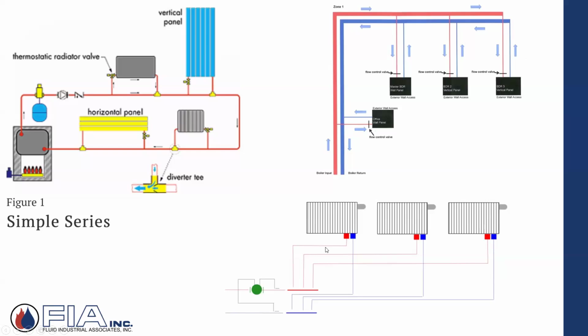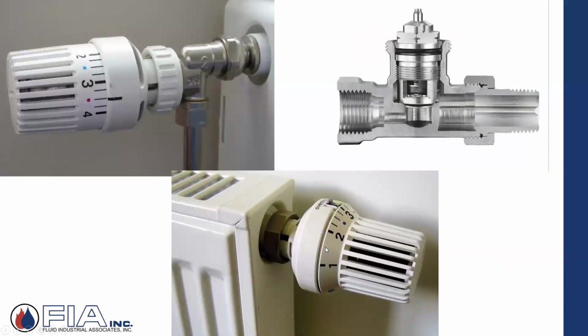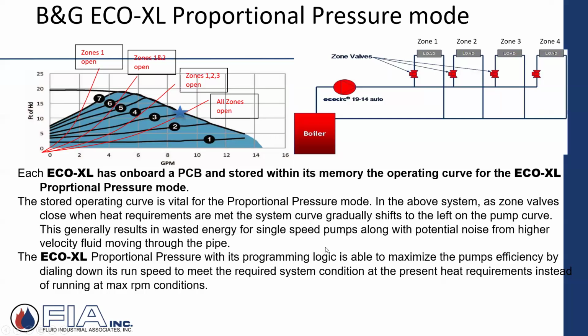These just happen to be non-electric valves as opposed to electric, but they could be electric. It doesn't matter. But it's a two-pipe system feeding terminal units. And those terminal units have a valve that closes so that they don't overheat the space. Pretty simple, pretty straightforward. This would be an exploded view of a non-electric valve where there's no wires. It's just sensing. This is popular in dormitories, maybe apartment buildings where they don't want to run thermostat wire and electricity. It's just a self-contained non-electric valve. What I want to show in this drawing here, this little screen here, is what's going on in that proportional pressure mode. So from the drawing on the right here, here's my mechanical system. I got a boiler, I have a distribution pump, and I have 4 terminal units. Pretty simple.